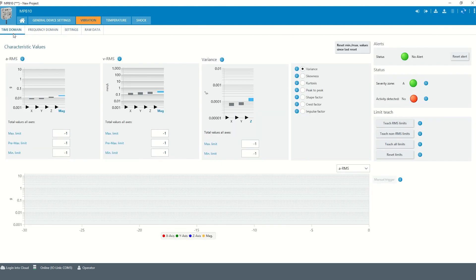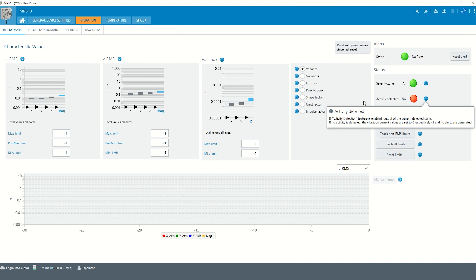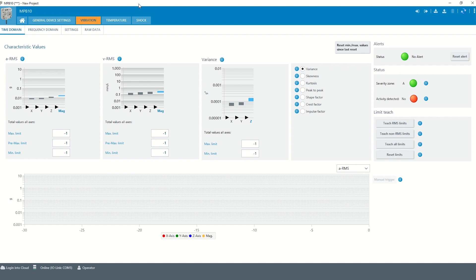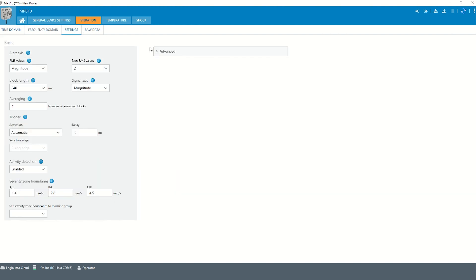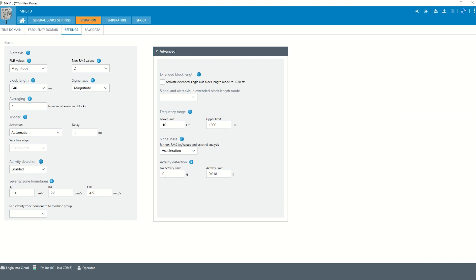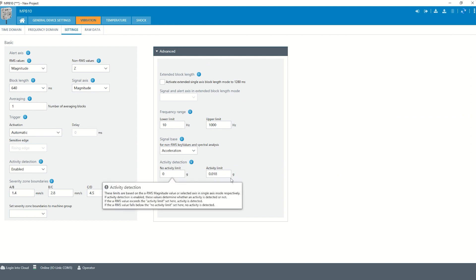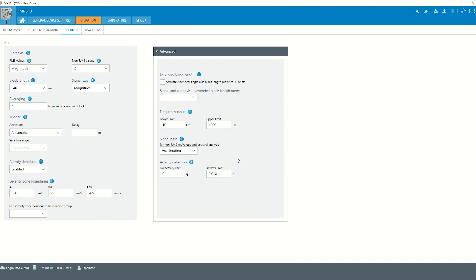If the activity detection is enabled and no vibration is detected, the vibration live values are set to zero and no alerts are generated. The limits which can be adjusted in the advanced settings are based on the a-RMS magnitude value. If the a-RMS exceeds the activity limit, an activity is detected. If the a-RMS falls below the no activity limit, no activity is detected.